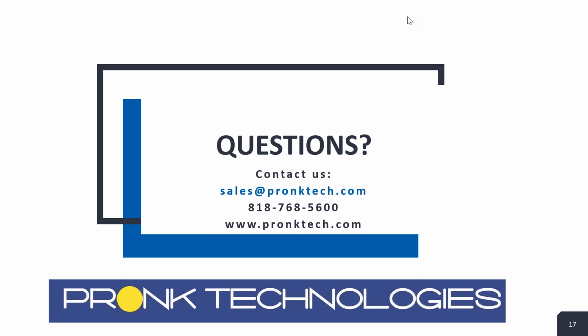Okay, so my current PM procedure doesn't require me to perform any leads testing for leakage. Is that something we should be doing? Yeah, leads, of course, is anything that comes in contact with the patient. It could be a patient safety issue. As a general rule, anything that comes in contact with the patient, it is highly recommended you do a PM on. Of course, if your organization has made a conscious decision not to do that, that could be acceptable. Just make sure you have it documented as part of an AEM program, maybe an alternate equipment maintenance program, that specifies that you're not required to do it and your justification for not doing it. But generally speaking, you definitely want to try to do leakage testing on anything that comes in contact with the patient.